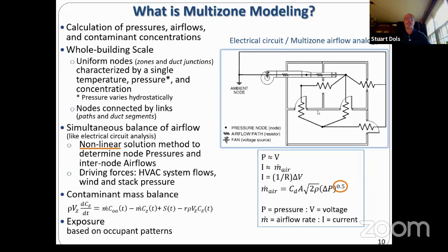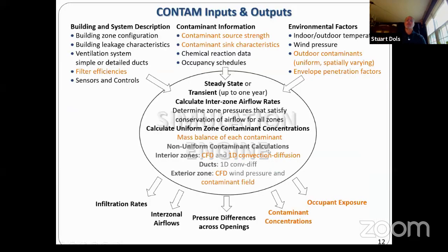Once we have pressures influenced by driving forces from the HVAC system flows, wind, and stack pressures, we can solve for air flows between zones and through ducts, form a contaminant mass balance on a large number of contaminants. Once we have those contaminant concentrations in the zones, we can perform exposure analysis of occupants within the zones, for simulations up to a year long.